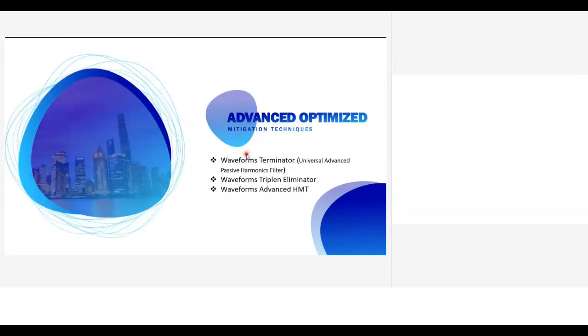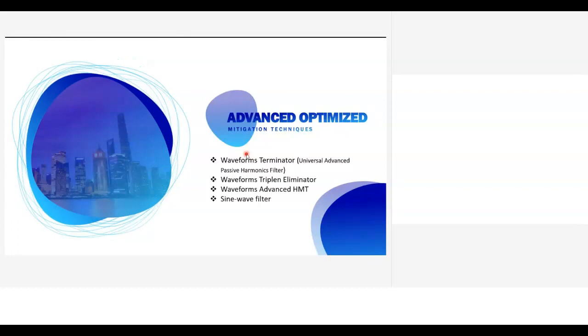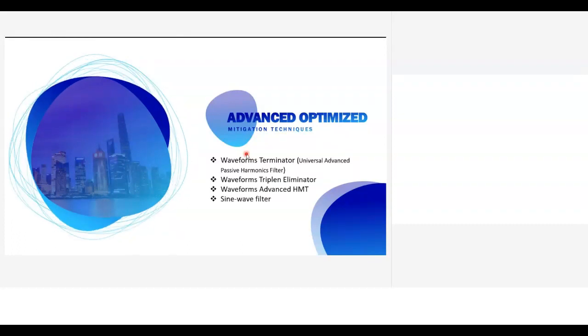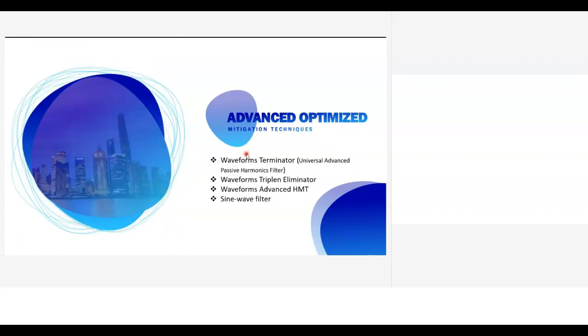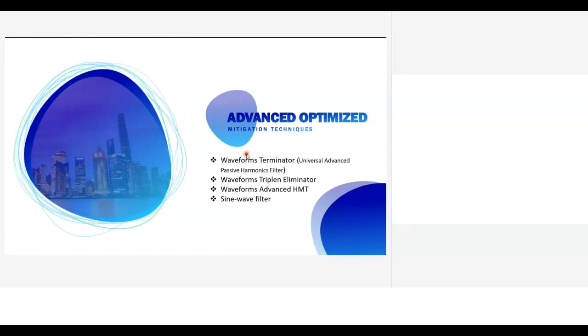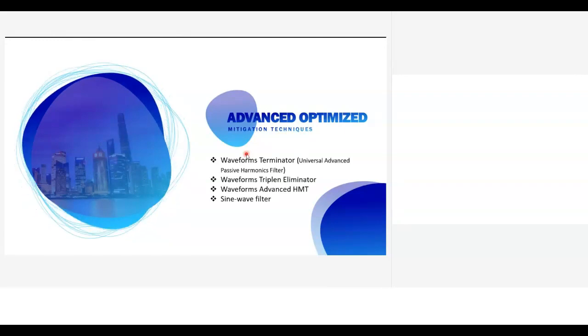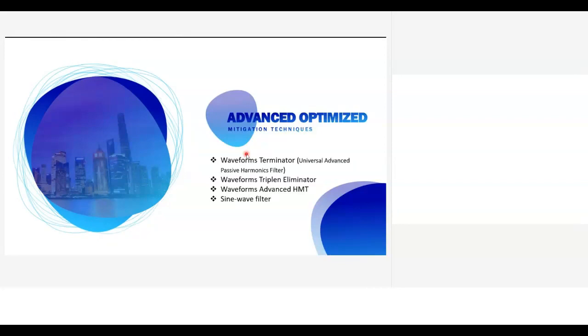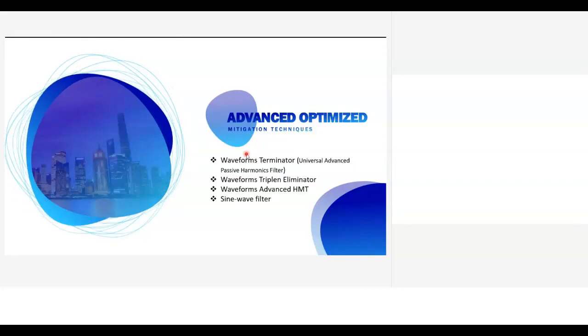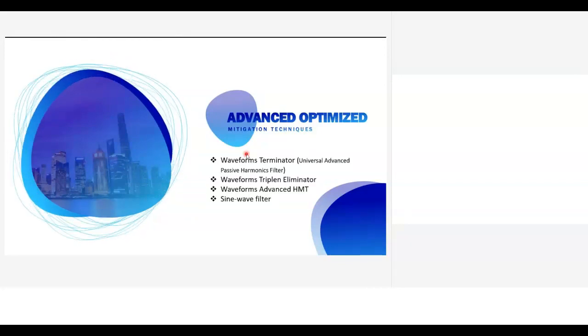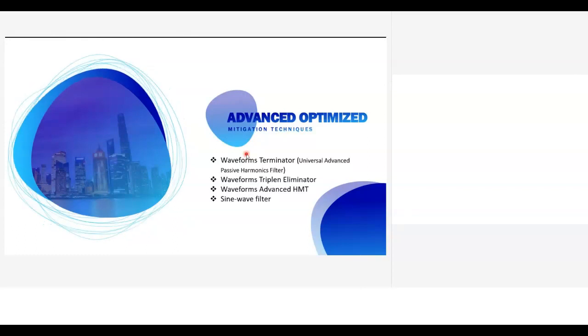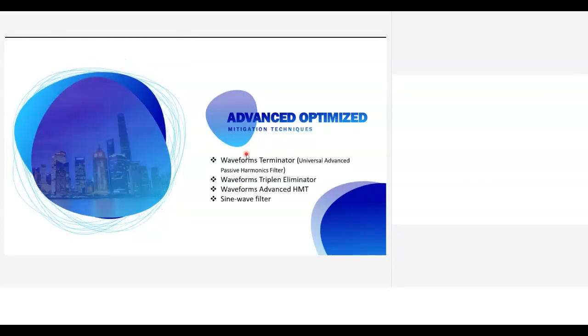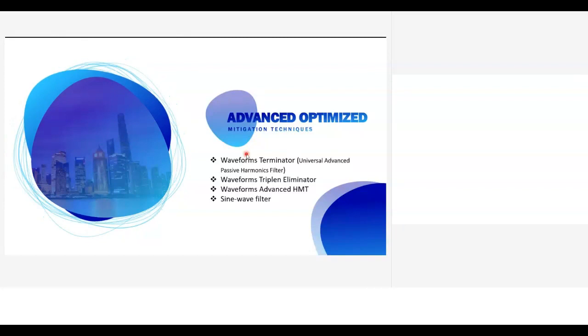So we call it waveform terminator, and we have waveform triplen eliminator. When you say triplen, it's the third harmonic: third, 9, 15. All these are triplen harmonics. Then we have the waveforms advanced HMT, which is harmonic mitigation transformer. Then we have the sine wave filter. Sine wave filter is not actually a reduction in harmonics, but is there to protect the motor and improve its performance.